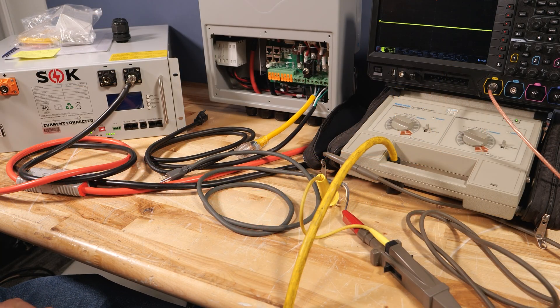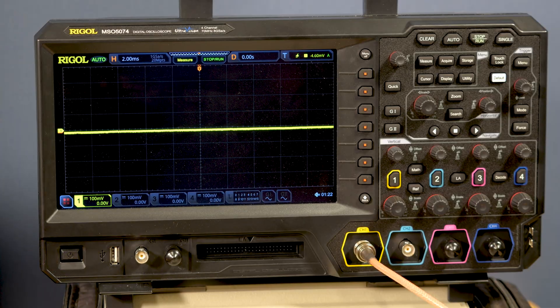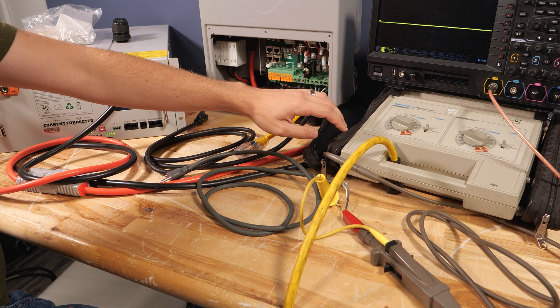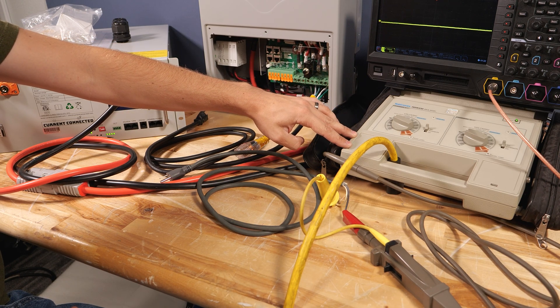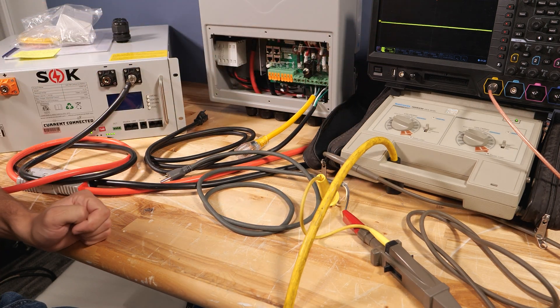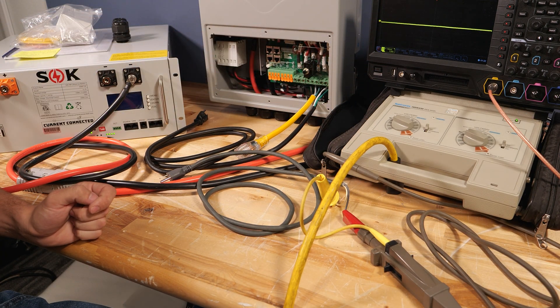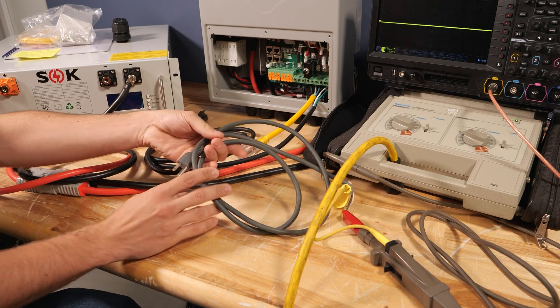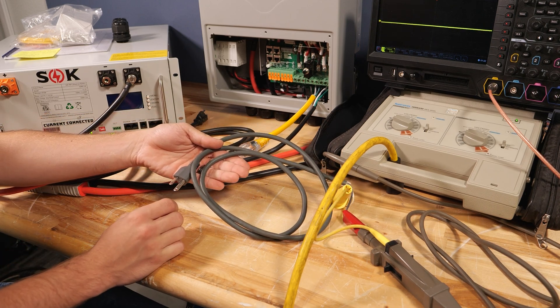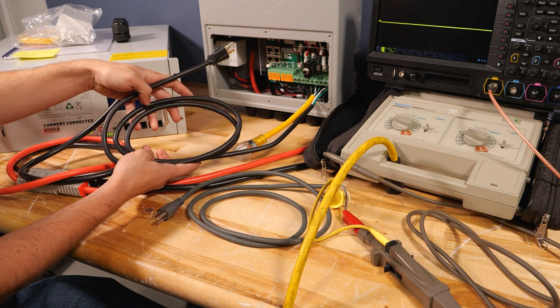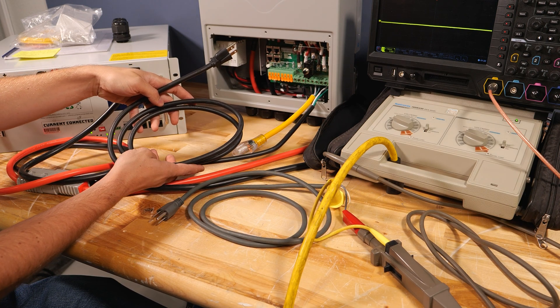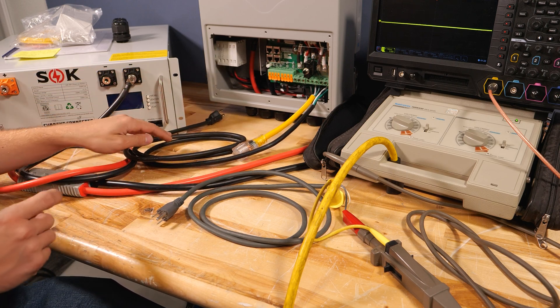Let's check the output waveform. I have my Rigol MSO 5074 oscilloscope set up and ready to go. My Tektronix isolator is set up. This is going to take the 120 volt signal as a differential input and feed it into the scope safely so that I don't blow up my scope. Right now I have an AC cord hooked up to the probe so that way I can easily select between the inverter power and grid and I did wire up an AC cord feeding the input of the inverter. We're not using that until our next test. I just wanted to get ready.